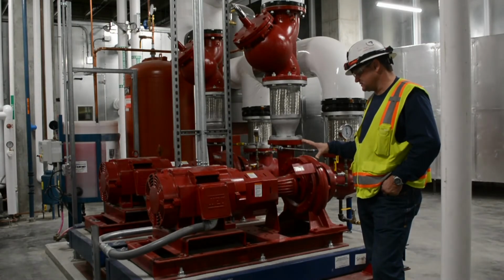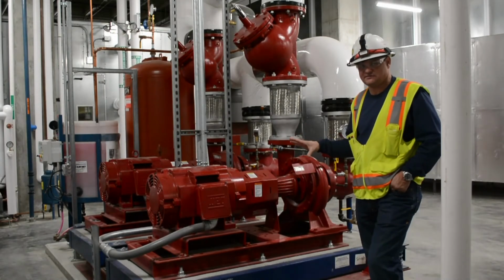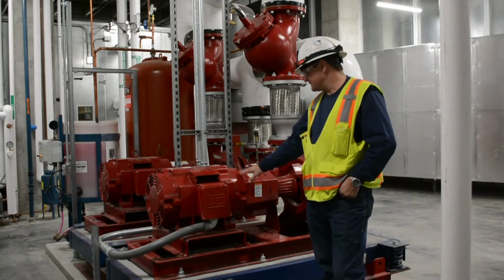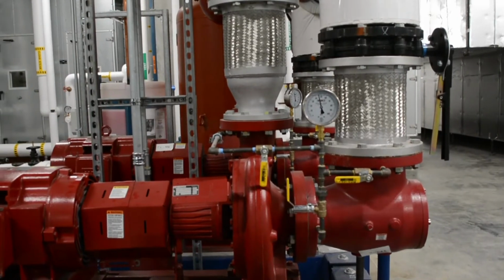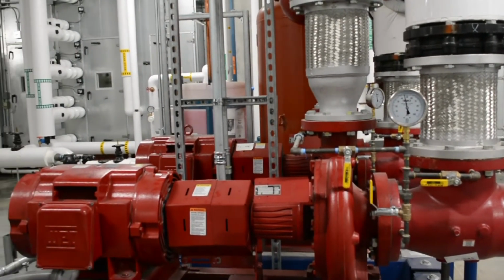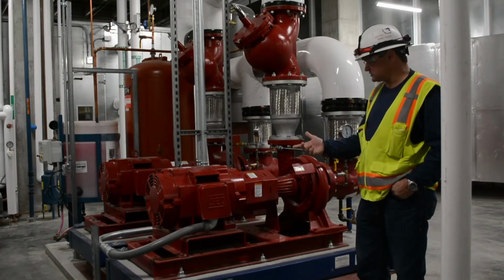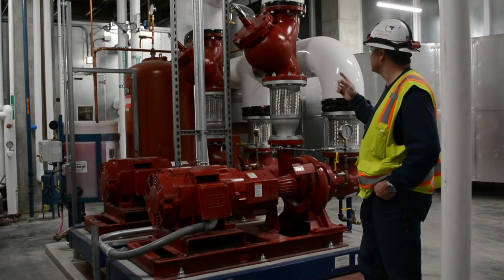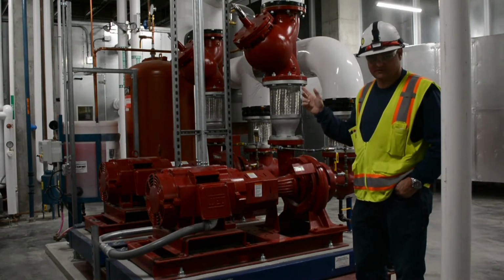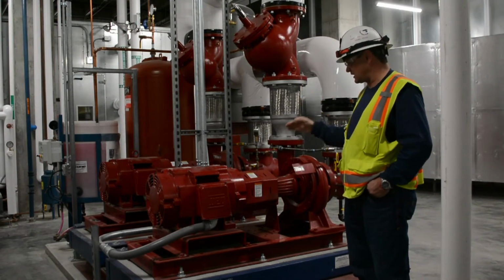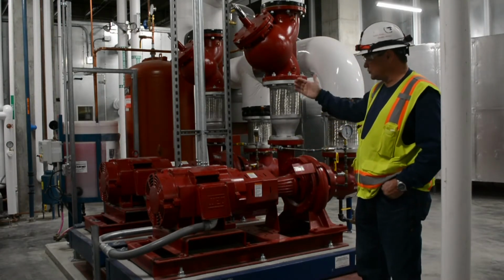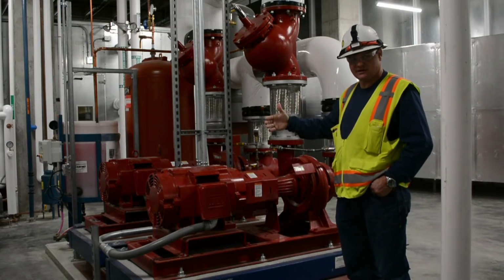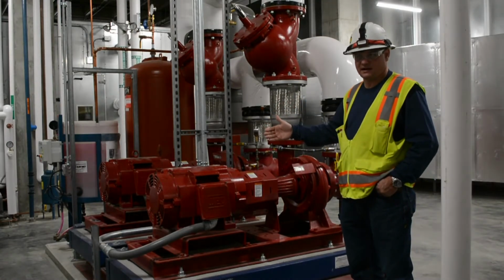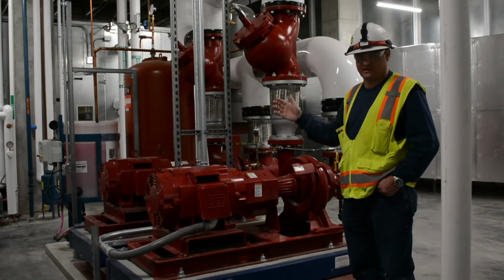Here is a Bell & Gossett 1510 series base mounted pump. This type of pump is typical to all the pumps on this project. This is a 25 horse model here that serves the heat recovery system. All right, so we're pumping glycol with this machine here. Duplex for redundancy. One pump only needs to run at a time, and that is typical of all the other pump skids on this floor.